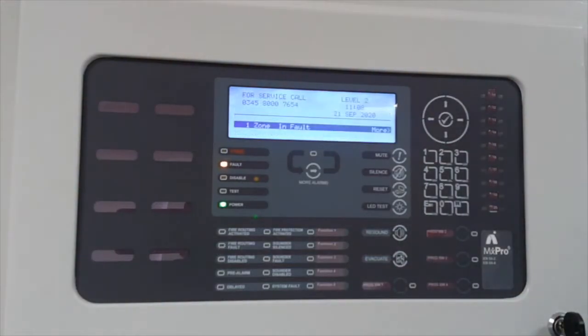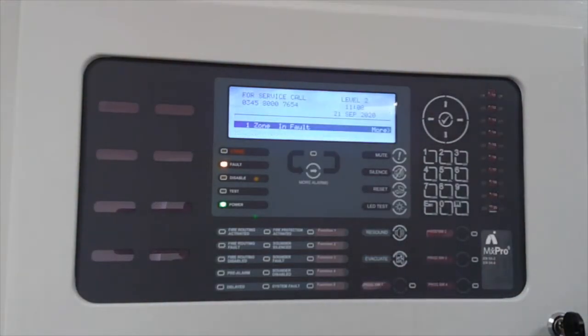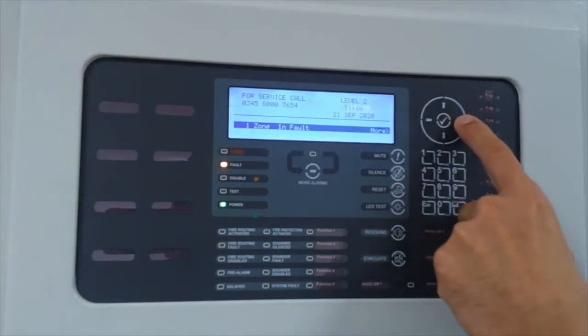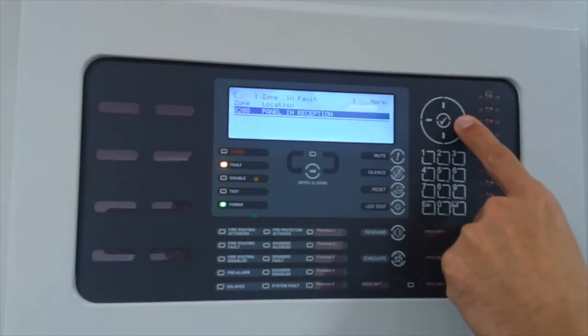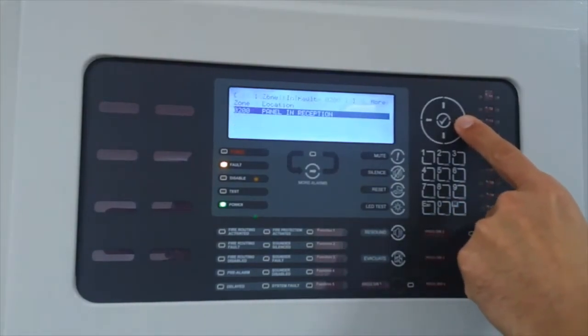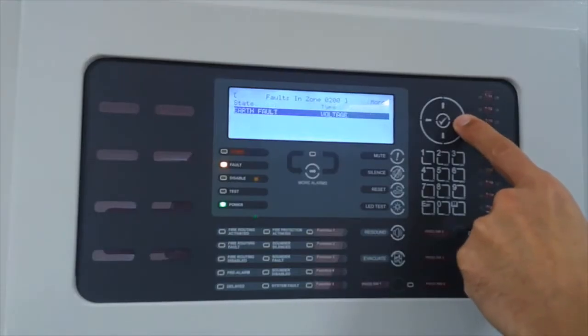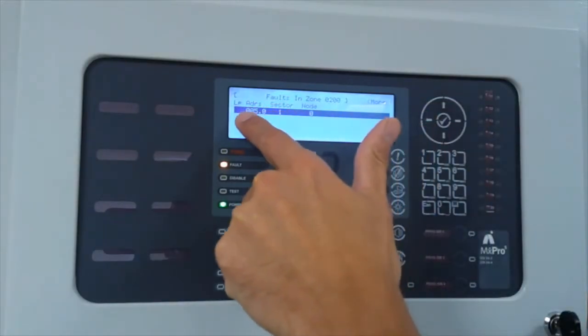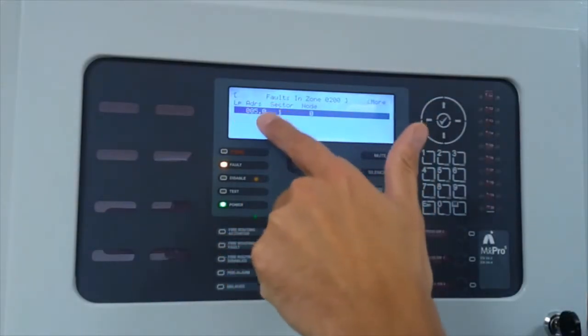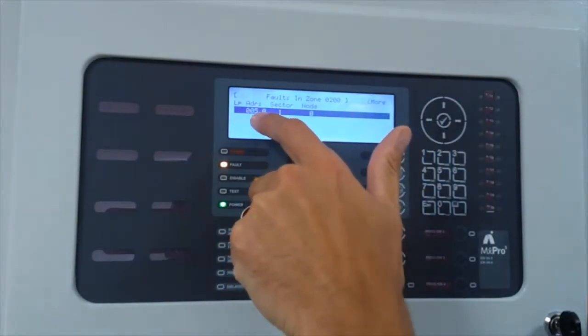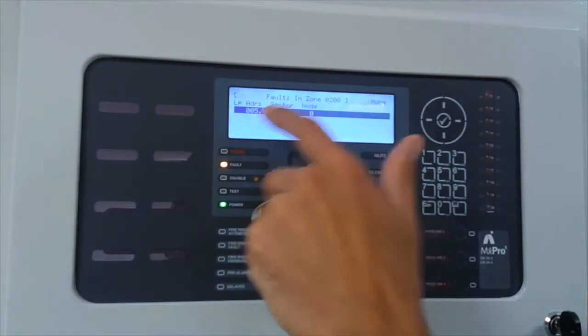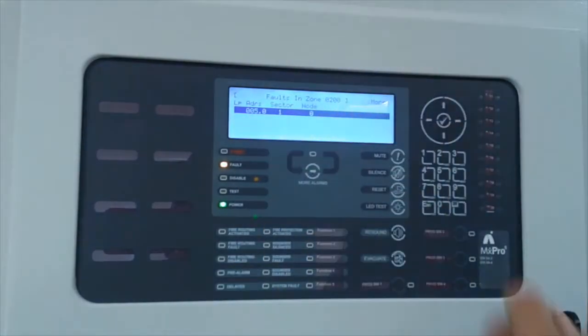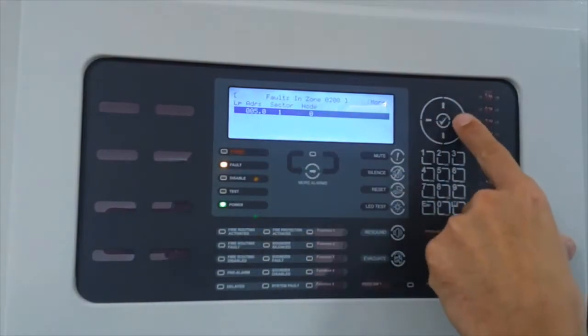So we can see we have a fault on the system. Scroll to the right-hand side, panel in reception. More information - earth volts, 16.8 volts, it is too high. Loop 0, address 5. Address 5 is your panel multimeter, what we have just shown you there on the panel multimeter itself.